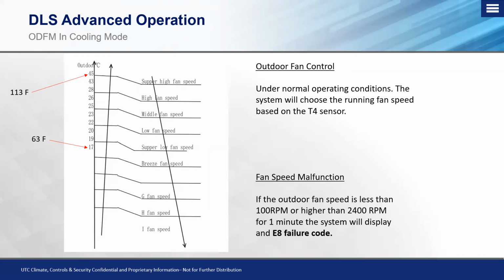Now in this case, without the service tool, we can ohm out the fan motor, check it to ground, make sure it has a secure connection, check the drive board that it connects to to make sure that it's outputting the correct voltage, and make sure that there's nothing stuck in the motor. But we weren't able to confirm what RPM that fan was trying to run at, or when it was running, whether it was too low or too high. This is something with the tool we can plug in and verify. So one of the many useful features of the tool is to be able to see the RPM and confirm why that E8 code is happening on initial startup.